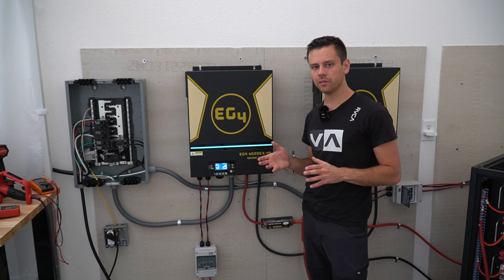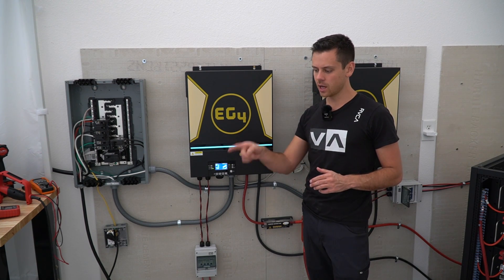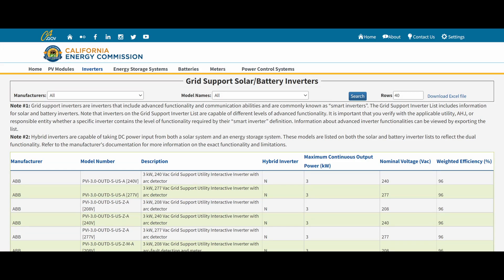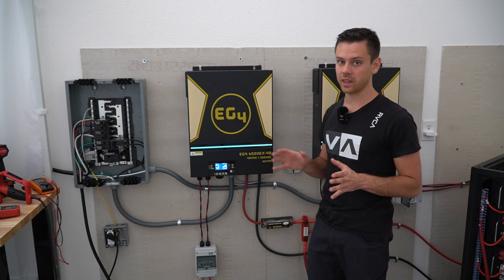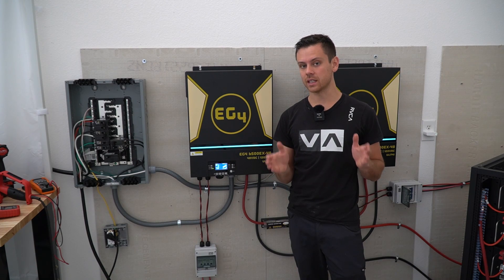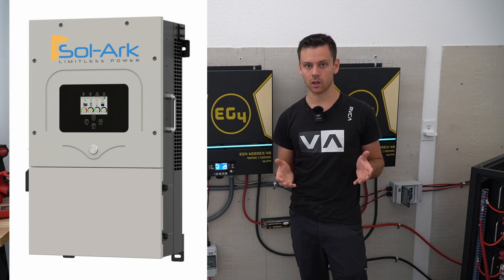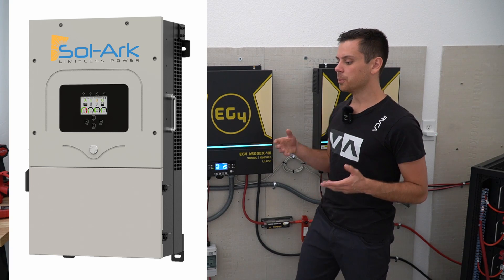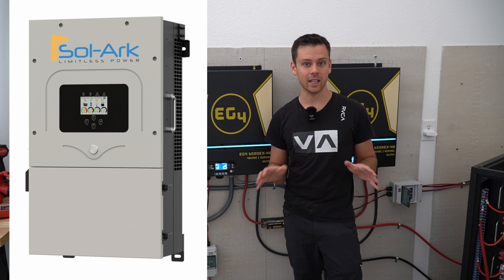All of these inverters — the EG4, the MPP, Growatt — none of these are on the approved equipment list for California. So if you specifically live in California, you will probably not pass inspection with any of these. I'm creating a new page on my website with an actual recommendation, and that's going to be the Sol-Ark. The Sol-Ark costs about three times as much as this model, but you will pass inspection anywhere.